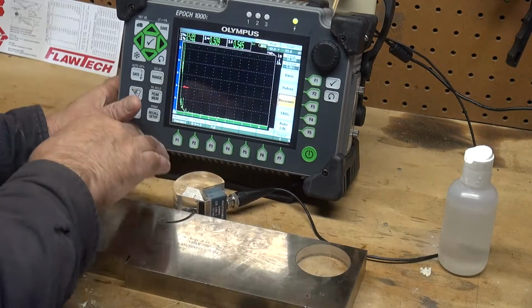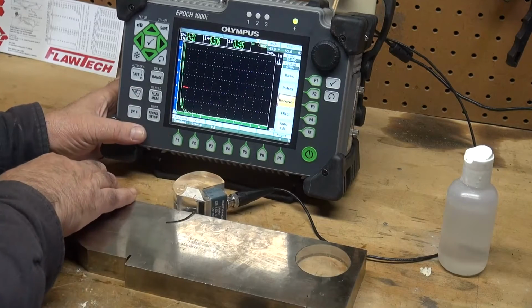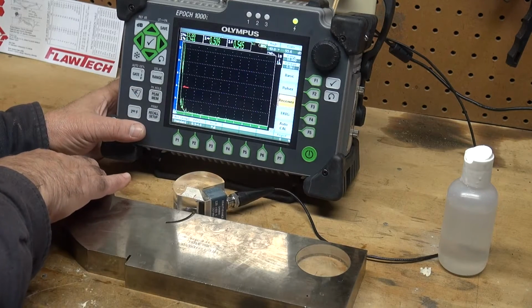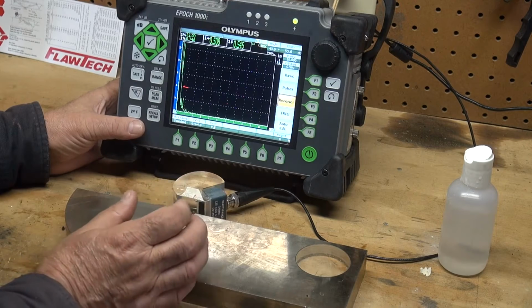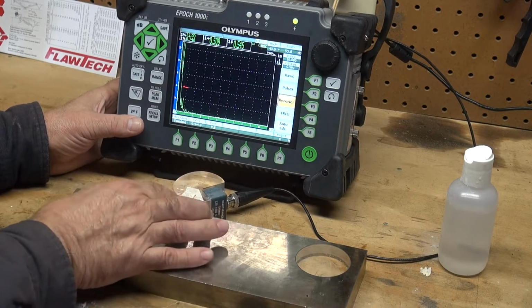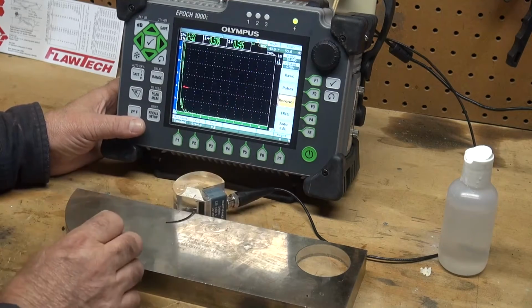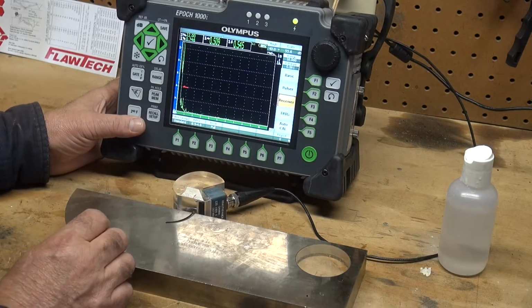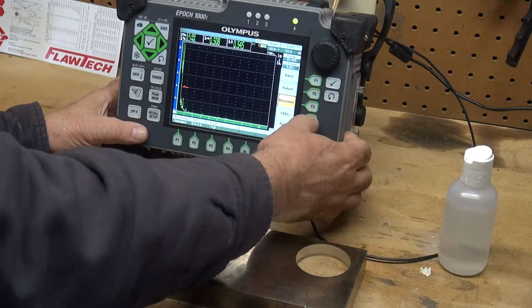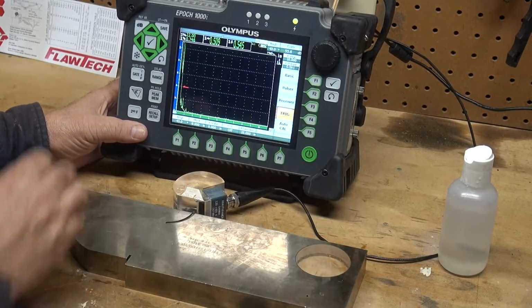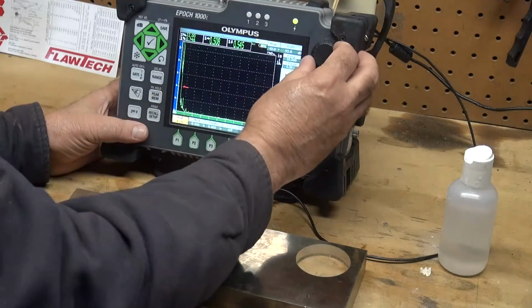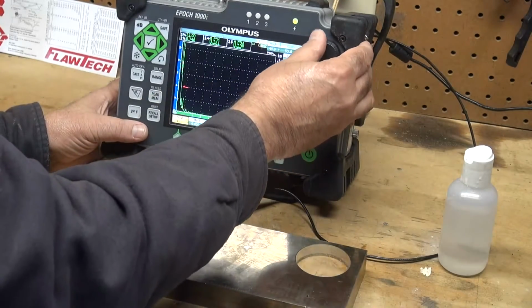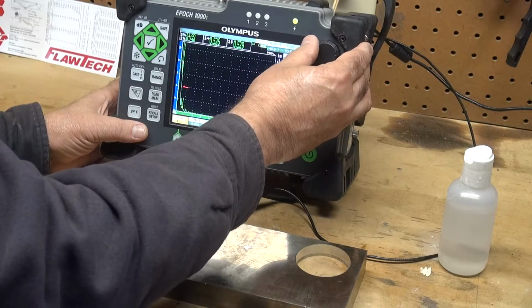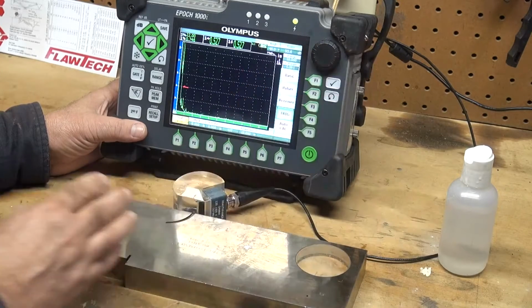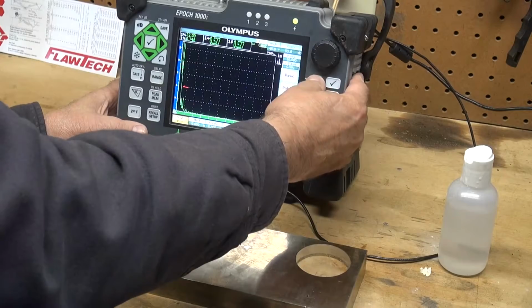Receiver, I have standard filtering and full wave rectification, and my filter is set at 0.5 to 4 megahertz, kind of in the middle. The 2.25 will fall right in the middle. And our trig function, I set my angle at 45 degrees because that's what my wedge is, and in this calibration process we will measure our angle.